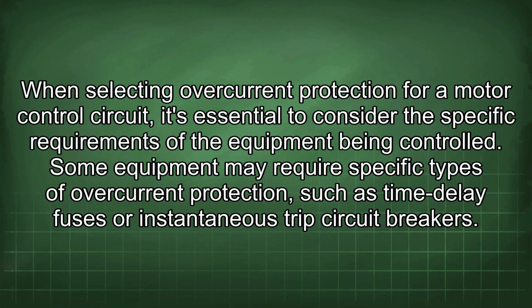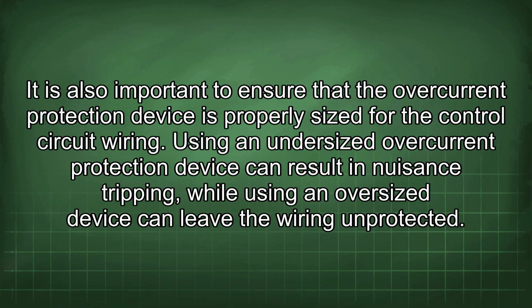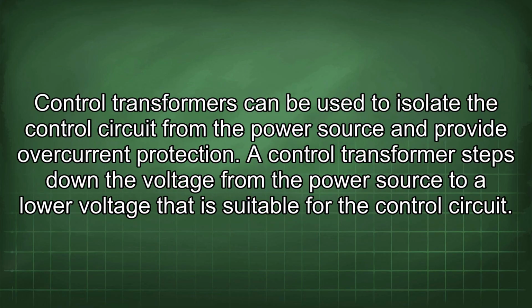When selecting overcurrent protection for a motor control circuit, it's essential to consider the specific requirements of the equipment being controlled. Some equipment may require specific types of overcurrent protection, such as time delay fuses or instantaneous trip circuit breakers. It is also important to ensure that the overcurrent protection device is properly sized for the control circuit wiring. Using an undersized overcurrent protection device can result in nuisance tripping, while using an oversized device can leave the wiring unprotected. Control transformers can be used to isolate the control circuit from the power source and provide overcurrent protection.